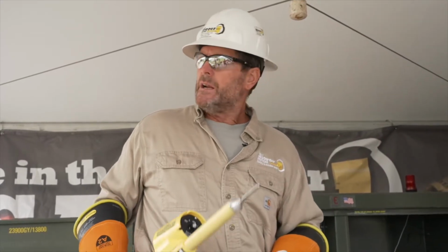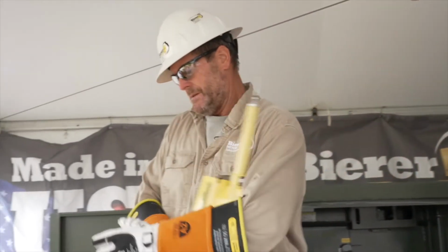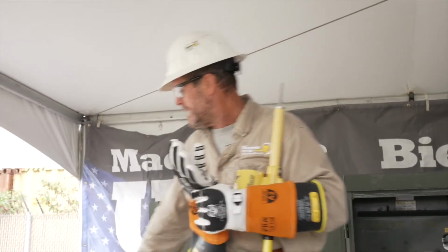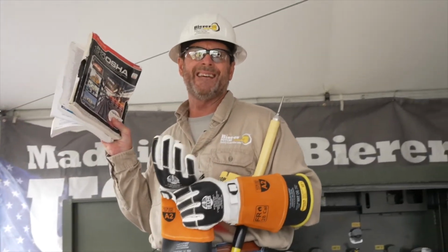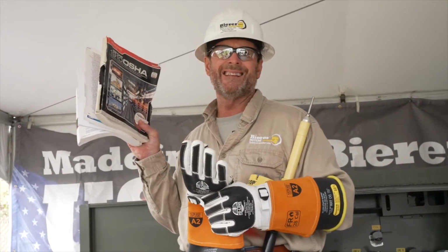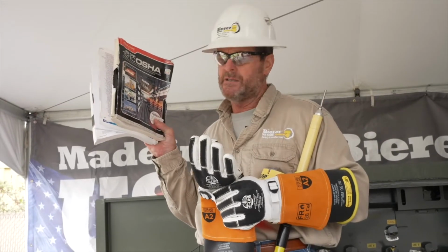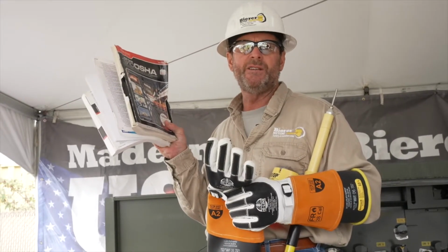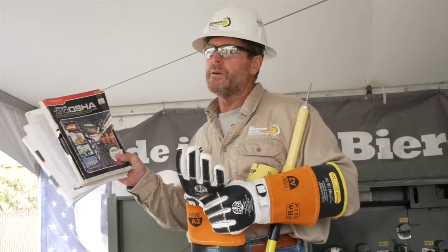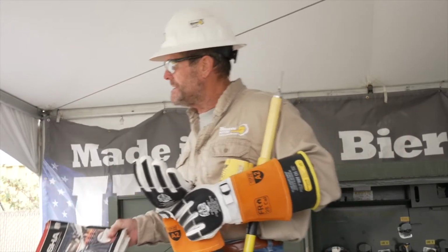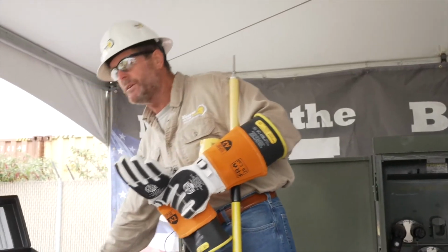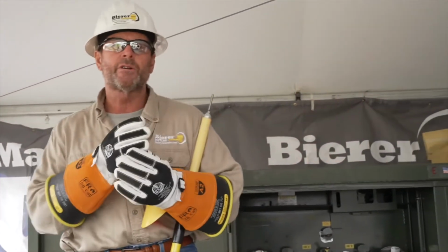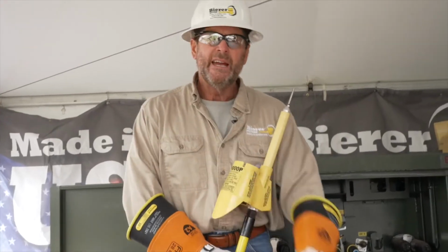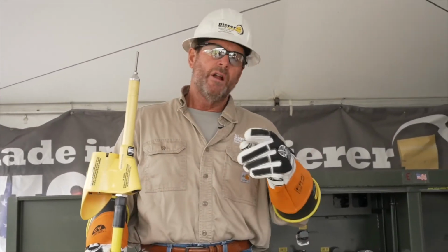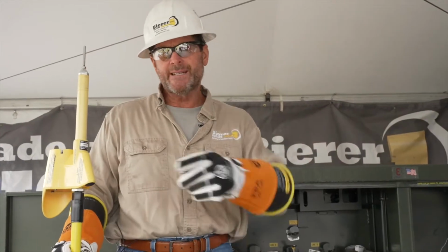But if we're going to talk about safety and what Brady Hansen calls your scriptures, OSHA 1910, we're going to go to 0.269. Under 0.269, lowercase n, it talks about your grounds, your TPGs, temporary protective grounds, and down to number 5, it says that prior to placing and installing your TPGs, you're going to verify that your conductor is de-energized of its nominal voltage. That's what it says.